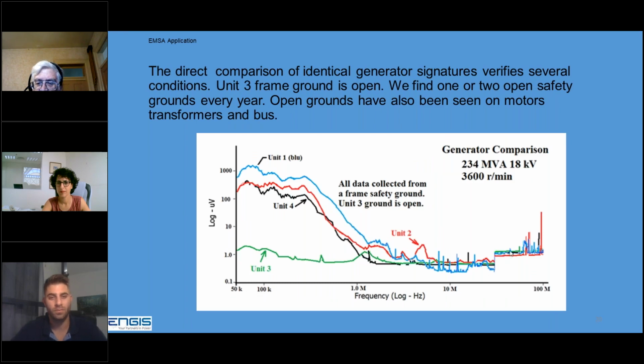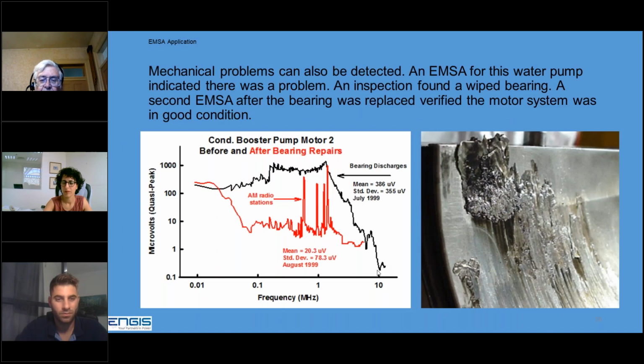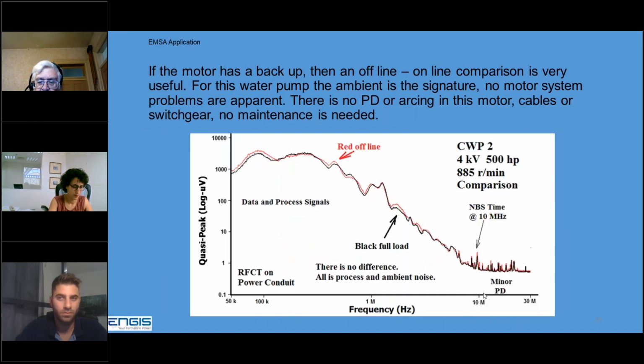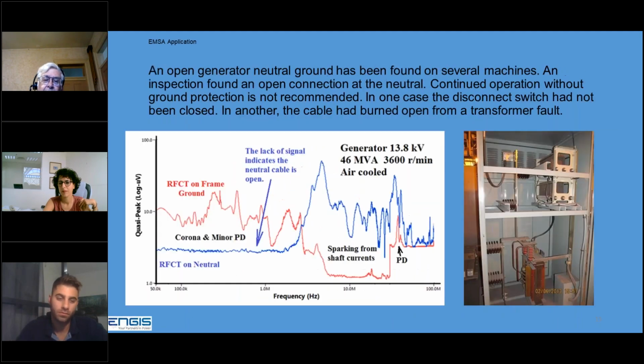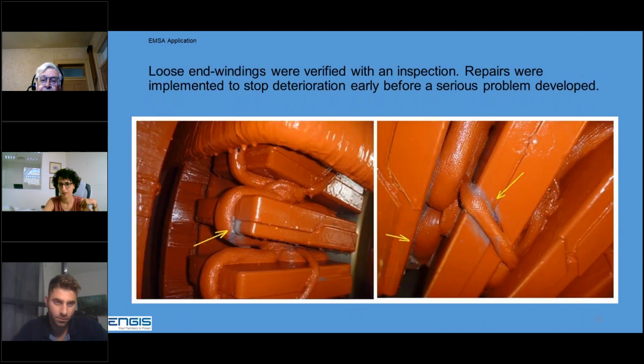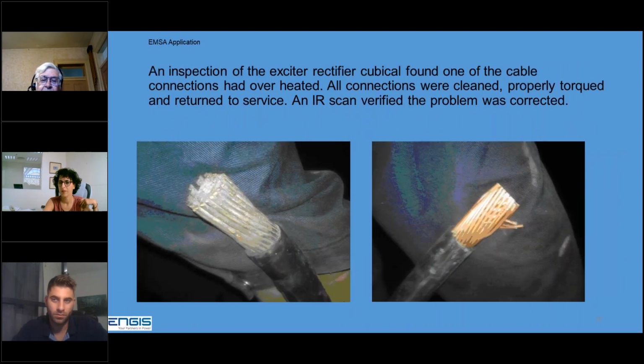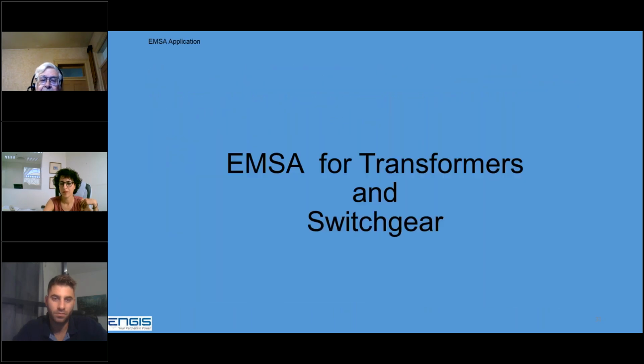So what Greg Stone basically looks at is this part of the frequency spectrum here, 80 megahertz and higher. What we have found is we need to look at all of these frequencies to pick up everything. And like I mentioned, especially for motors, this particular one, there's almost nothing above 10 megahertz. We stop at 30 megahertz. So looking at this frequency range with partial discharge analysis for 4 kV equipment doesn't pick up anything till it's almost ready to fail. And they recognize that and admit it. You've got to look at these lower frequencies for 4 kV and 3.3 kV equipment. And for other problems, like what we're doing for exciters, looking at these lower frequencies is very important, and PDA doesn't look at that at all.